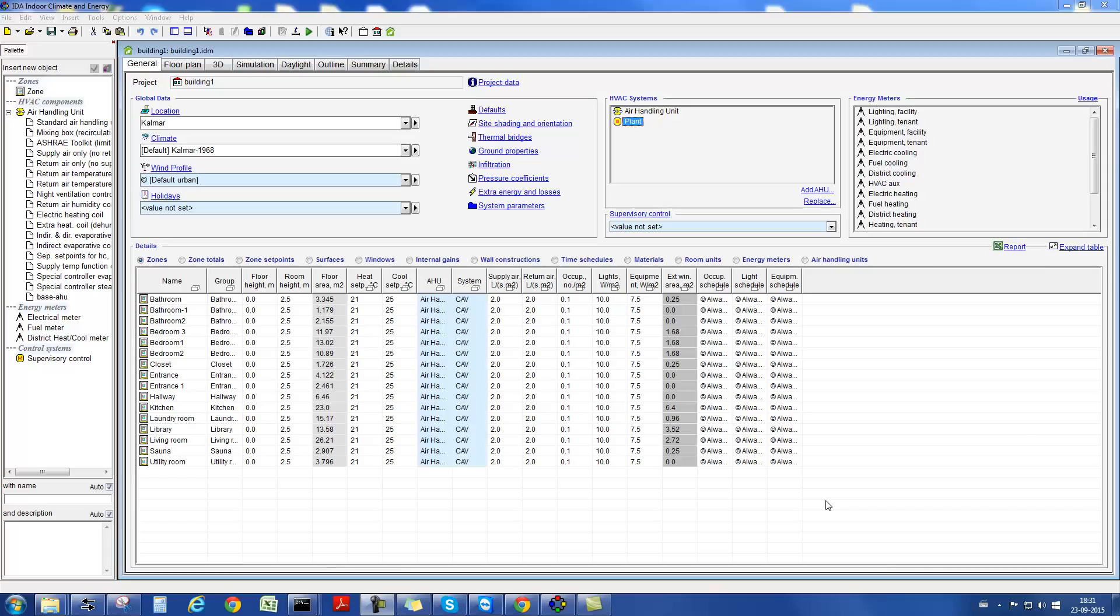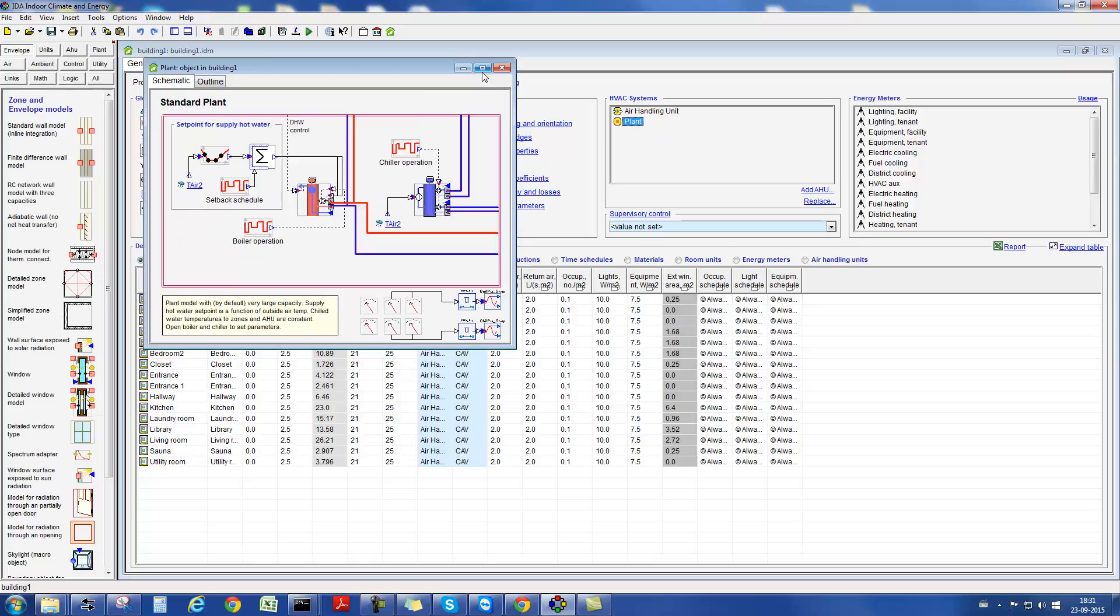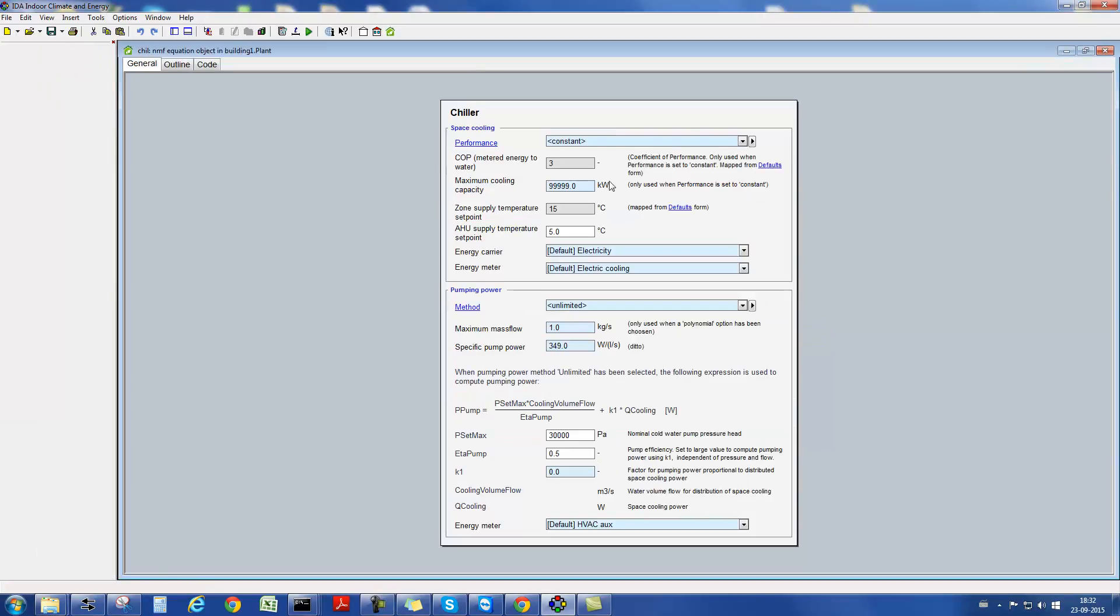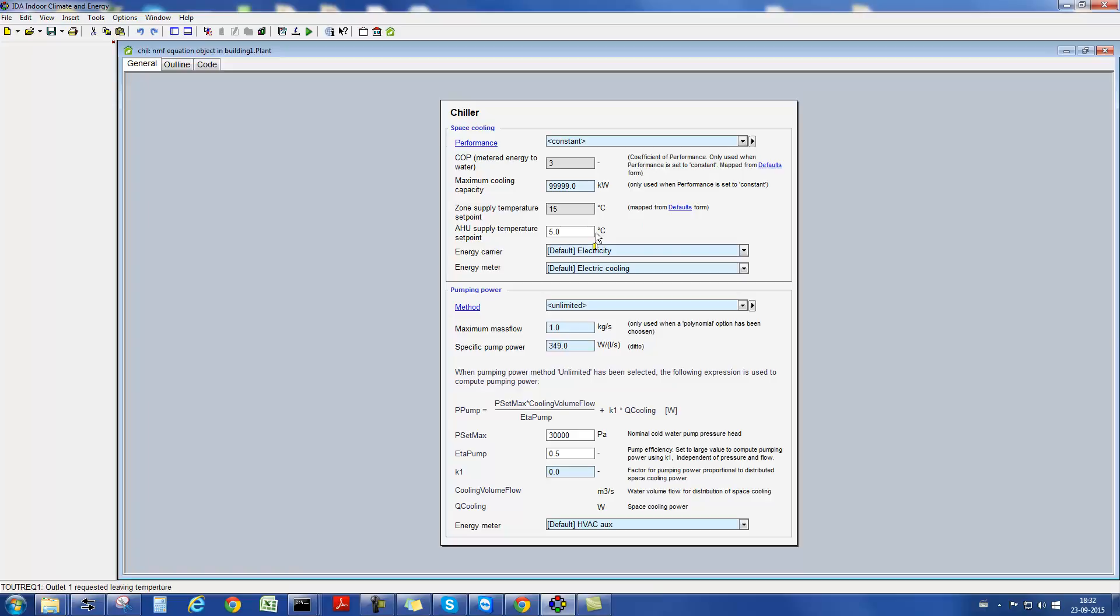Lastly, we want to talk about generation systems. Every IDA ICE model contains a chiller and a boiler, which supplies tempered water to the air handling units and the local supply units. These are simple models with a constant COP. There are also certain maximum capacities and settings for the supply temperature to the air handling units and supply units.